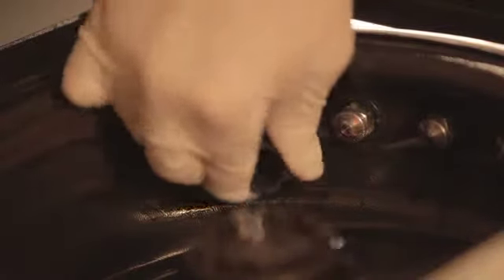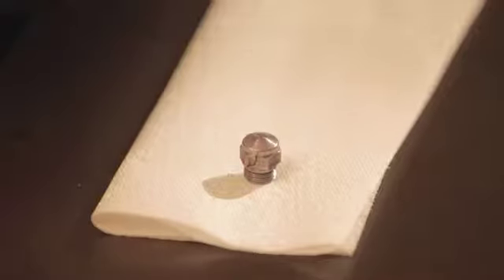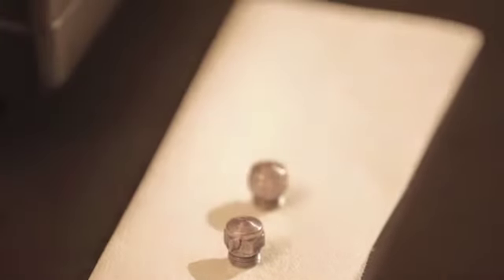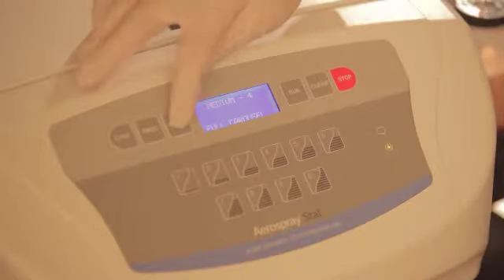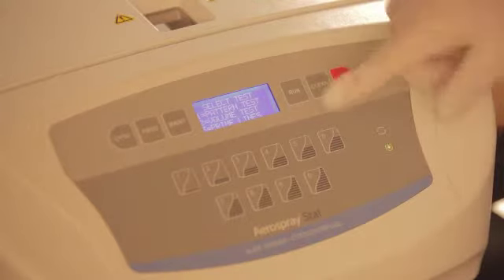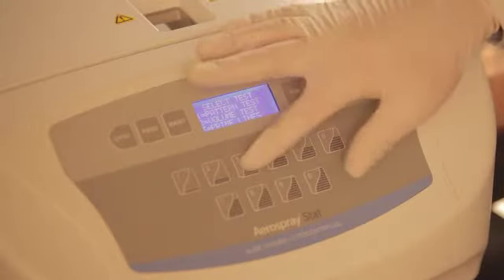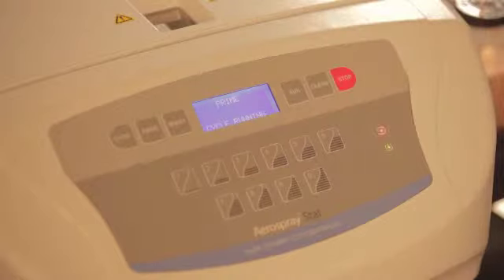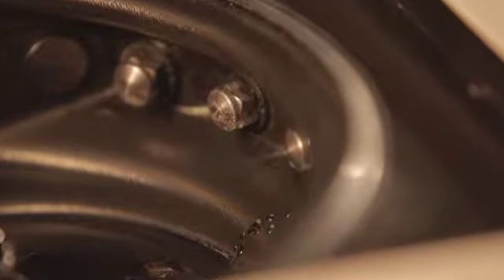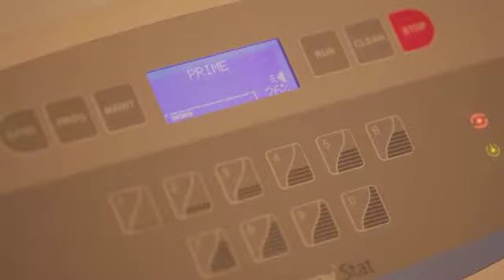The nozzles are removed by using the nozzle wrench found in the nozzle maintenance kit. Turn the nozzles to the left to loosen and remove. Place the nozzles in order, either on the counter or on the stainer near the bowl. Press the Maintenance button and Option 4 for prime lines. This will start a sequence when reagent in each line is pumped. 200 to 250 milliliters of each reagent will be sprayed through the respective lines. The level of reagent will go down quite rapidly during the process.